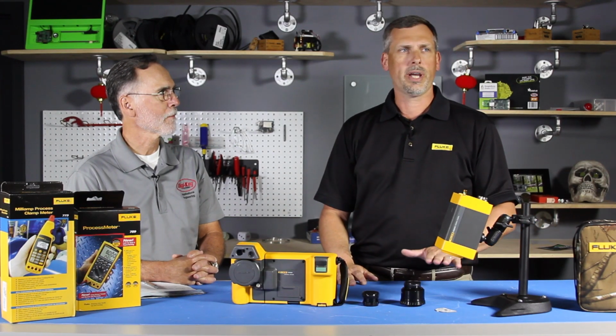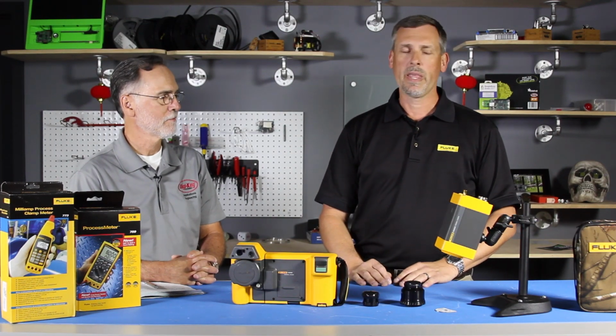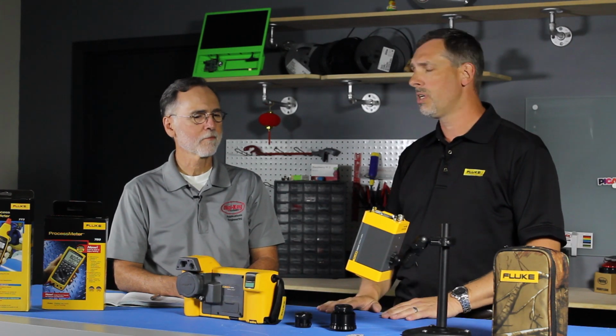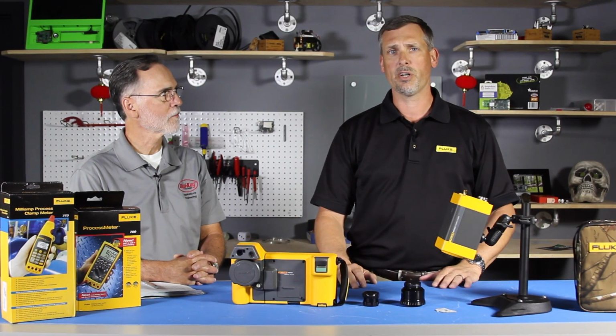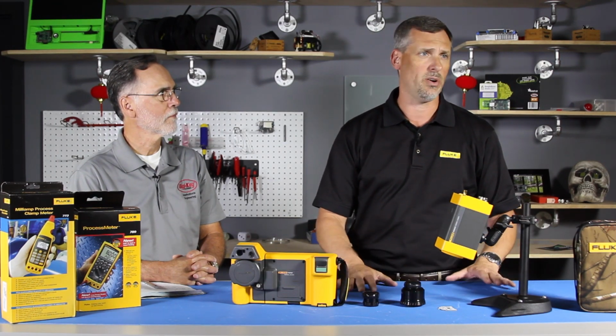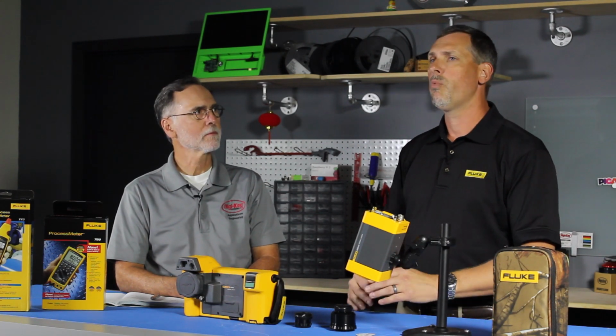Yeah. So you're looking at motors, pumps, electrical, and electronics a little bit from a PLC or a DCS kind of more traditional control system setup. Now this technology is migrating into electronics more and more rapidly, in aerospace and semiconductors. Anywhere anybody is using a printed circuit board, they can use a device such as this, any form factor with good enough resolution to identify an issue on a printed circuit board. You've got a hot trace, you've got high resistance, you've got components in two channels. Channel 1 looks a little bit warmer than channel 2, yet they're supposed to be acting the same way. Now you can identify that one's not acting the way we thought it was, or engineered it to be. We need to take a look at that.